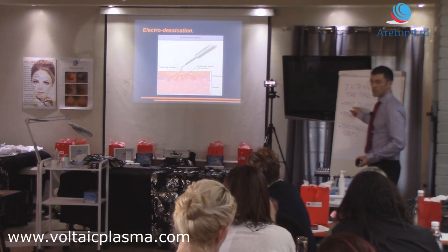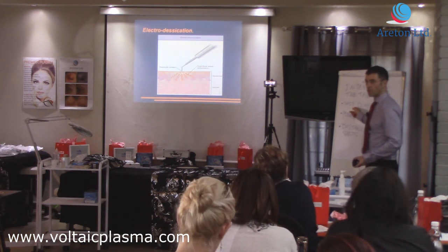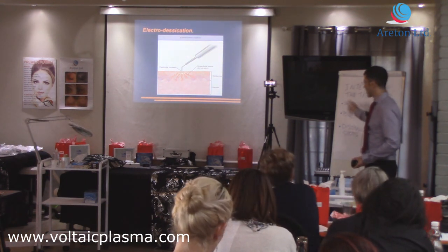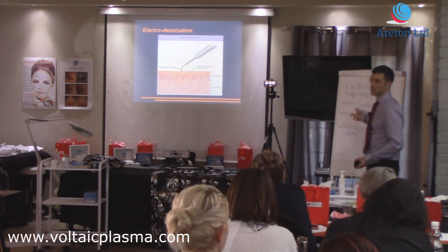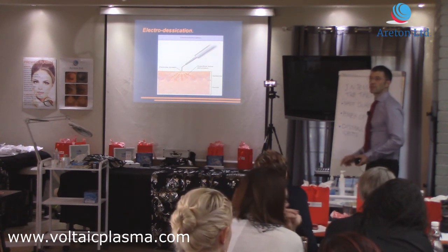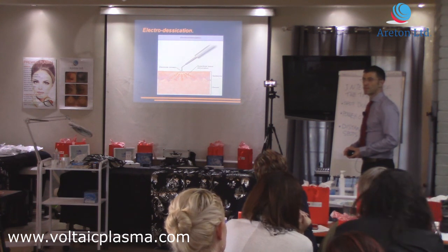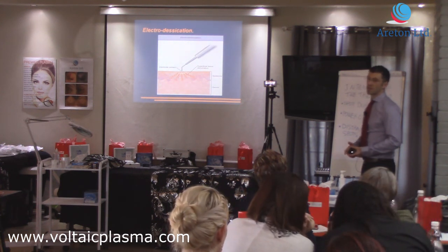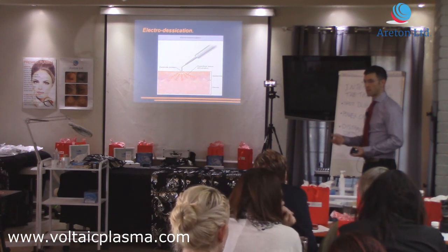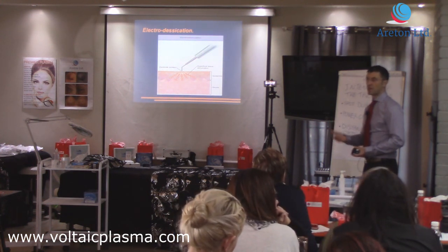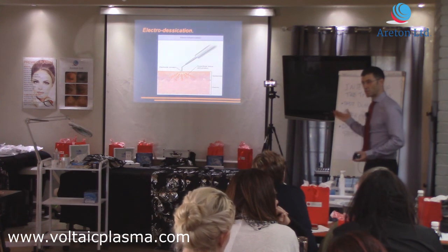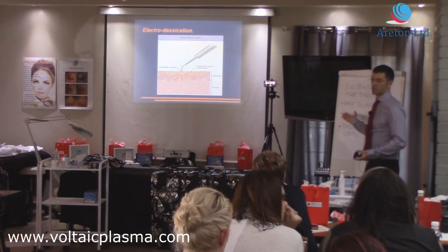So in the new device, you're going to be able, in a certain way, actually in two ways, to control that digitally. You can tell the device, please keep that arc on for at least 400 milliseconds. As soon as the arc comes in, it counts up to 400 milliseconds, so you know it's been on for at least 400 milliseconds.